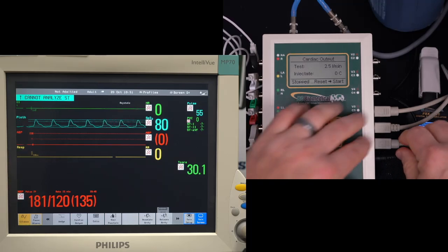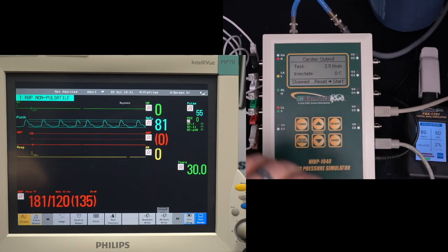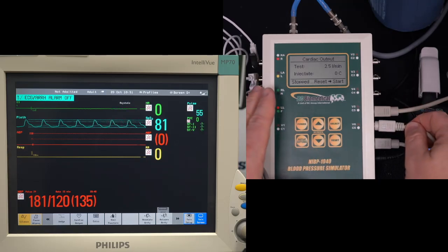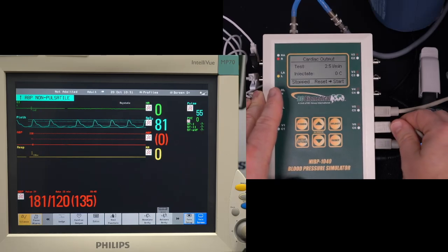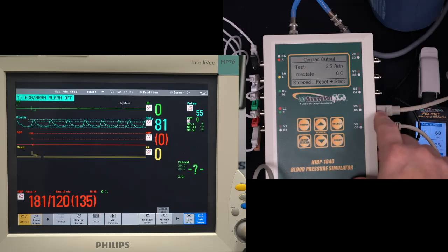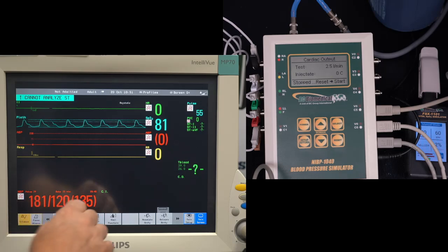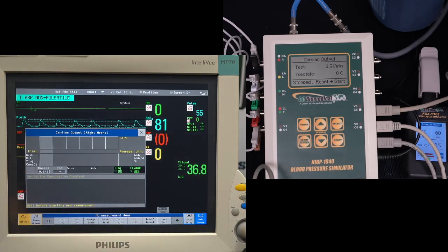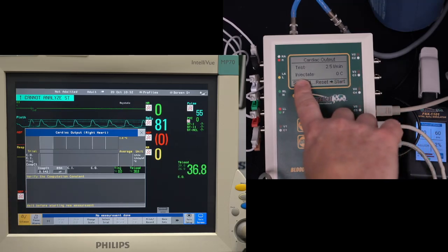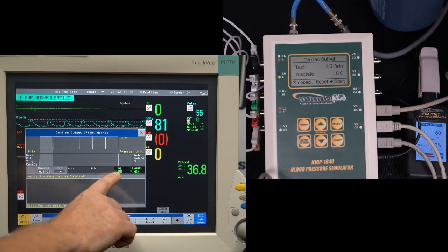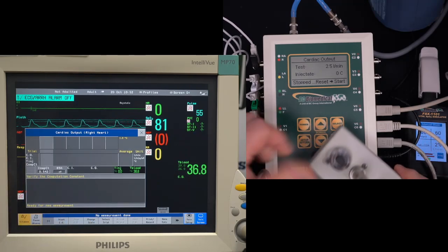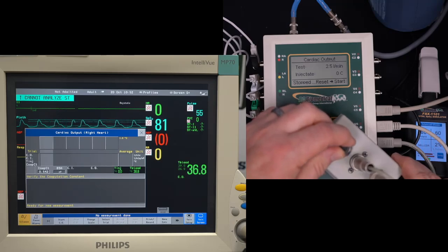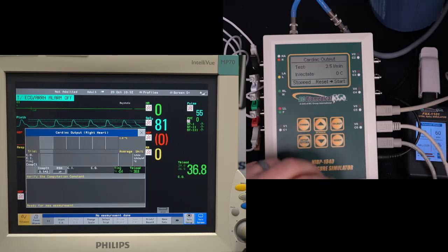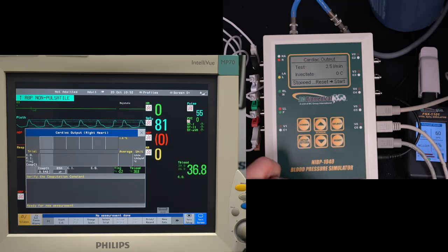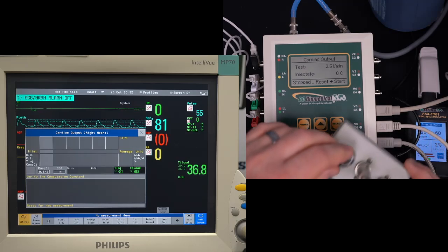Some monitors have a single cable that goes directly to the monitor. Some of them have this little breakout box. So you just need to be mindful of which monitor you're testing. We do have different accessories and different cables for those. Now, when you're doing the cardiac output test, we need to make sure that the configuration we have for the injectate matches, that the monitor reads the same temperature, and that's what is adjusted with this dial here. So as I turn this, the injectate temperature changes. So we want to make sure that the monitor is measuring the same temperature that we're simulating. We're simulating 0 degrees. So I'm going to adjust this knob until we get 0 degrees on the screen.